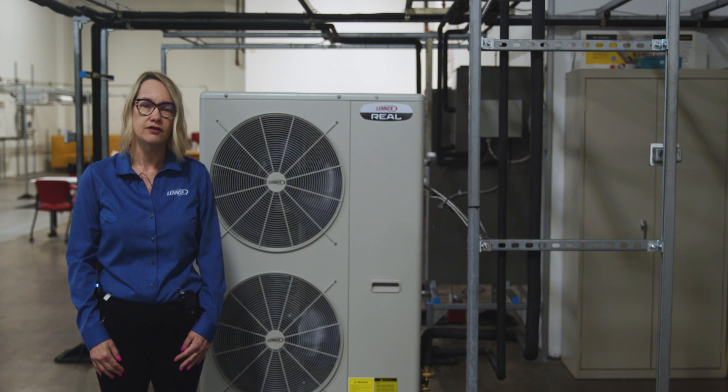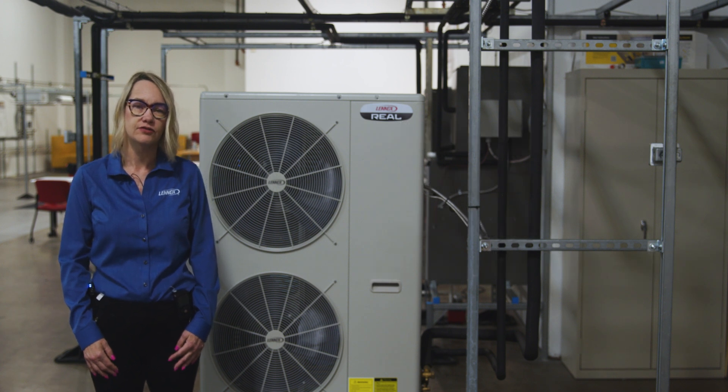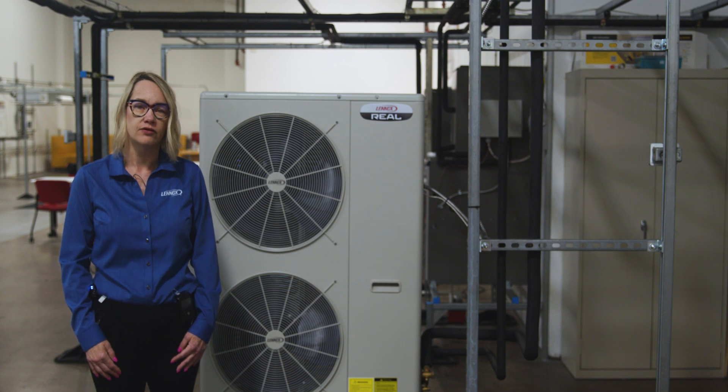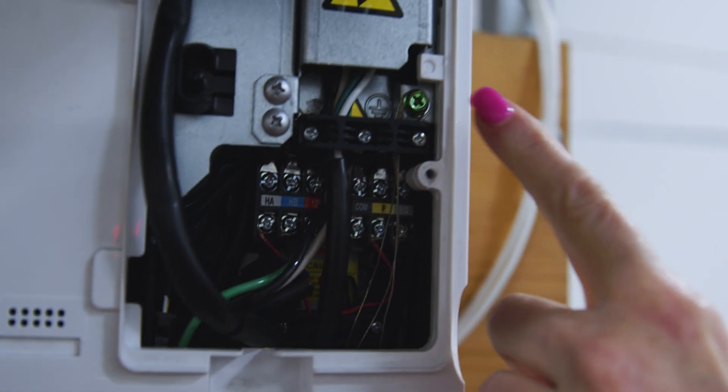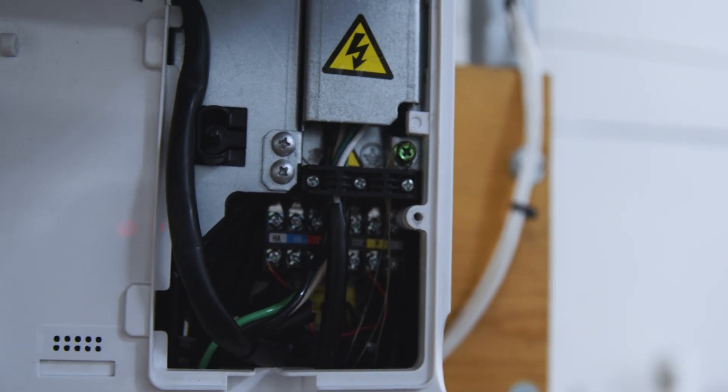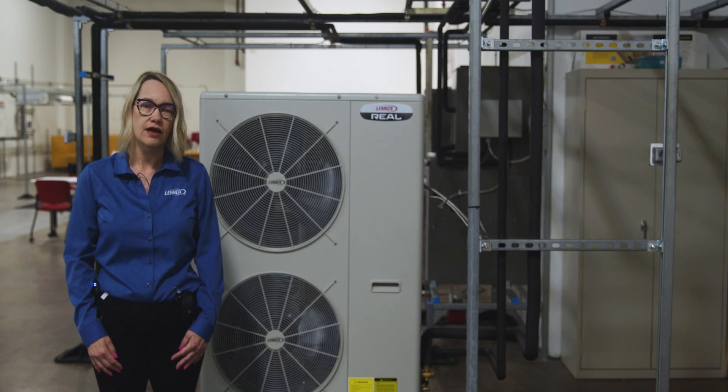The communication wiring is a continuous daisy chain from the condenser to each indoor unit in series. No splices are allowed. We ground the shield directly to the chassis screw on the unit. We connect the shield at each end of the run, and tie the shield together along the run.